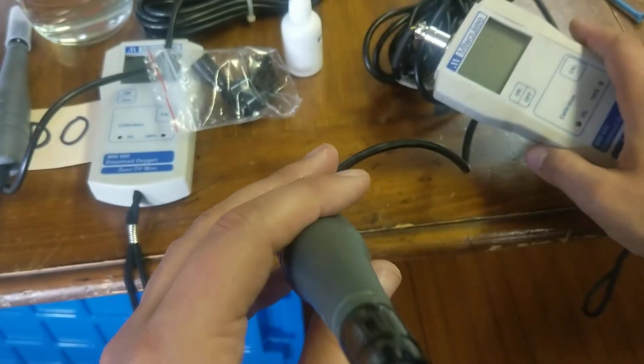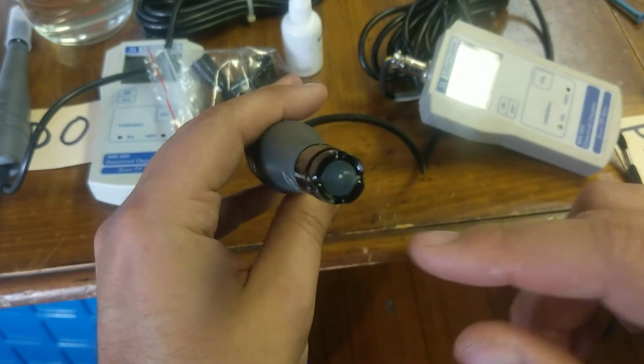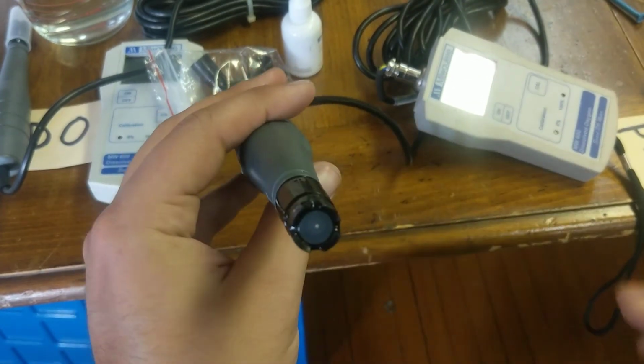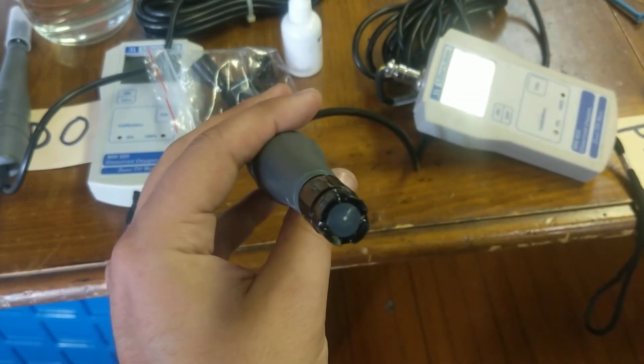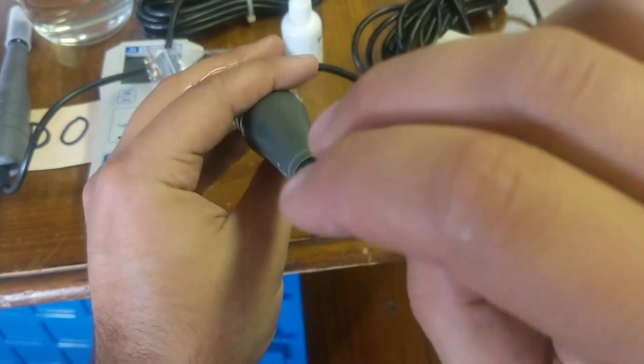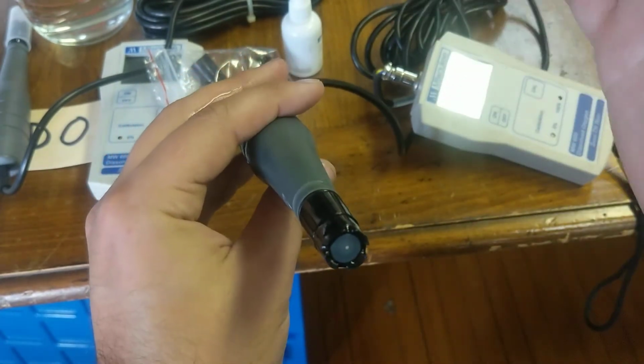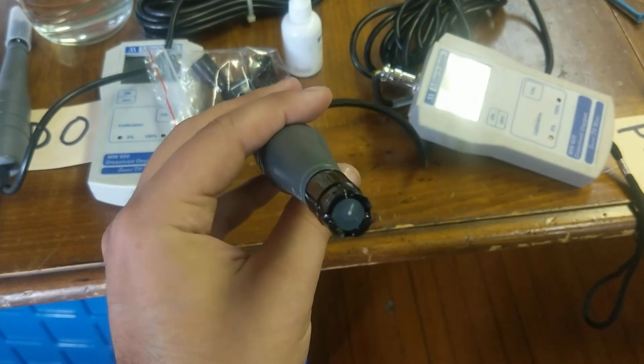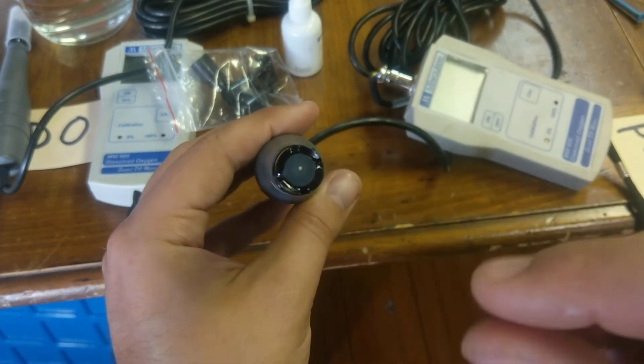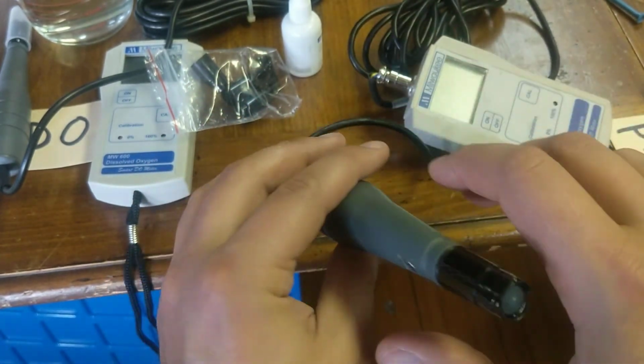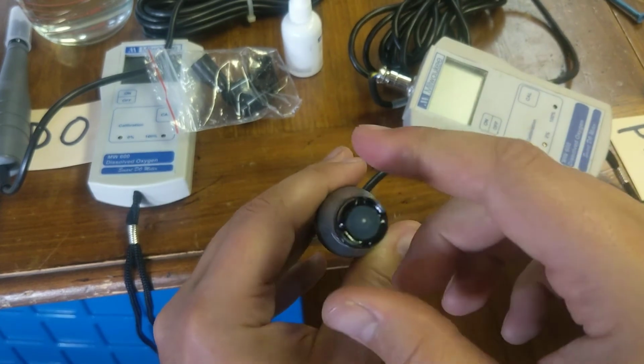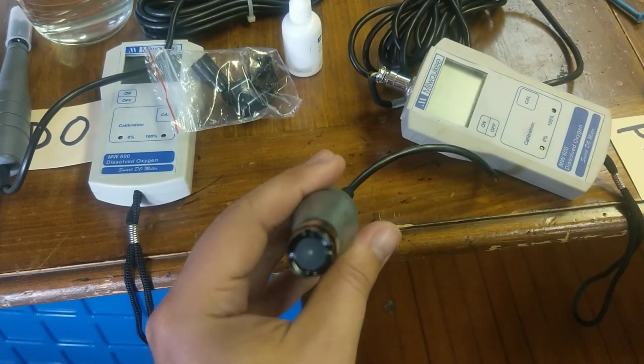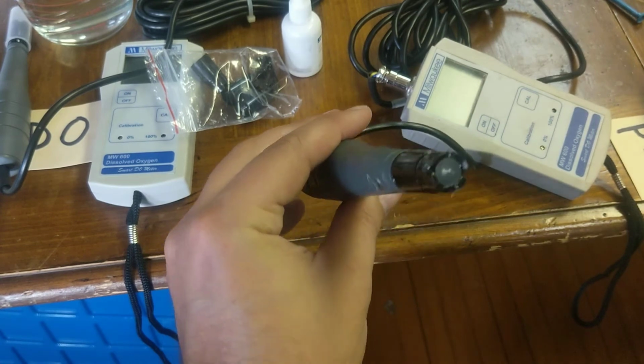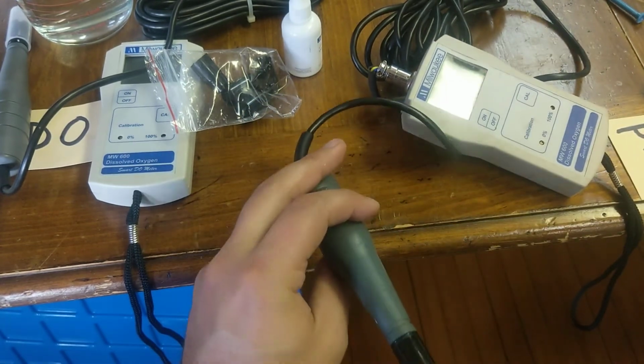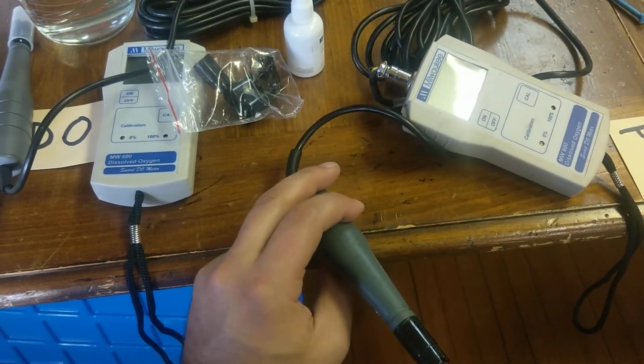Let's say you do have some bubbles on the bottom, some big ones. You want to take this off again, tap it, and then put it on again after that. You can also take it off a little bit, tap it so that it releases those air bubbles, and then put it back on. If you lose too much fluid, you'll want to put a couple extra drops in there. But I got it on the first try over here, and that tapping definitely helped over there. Once that's done, you can now calibrate it again.